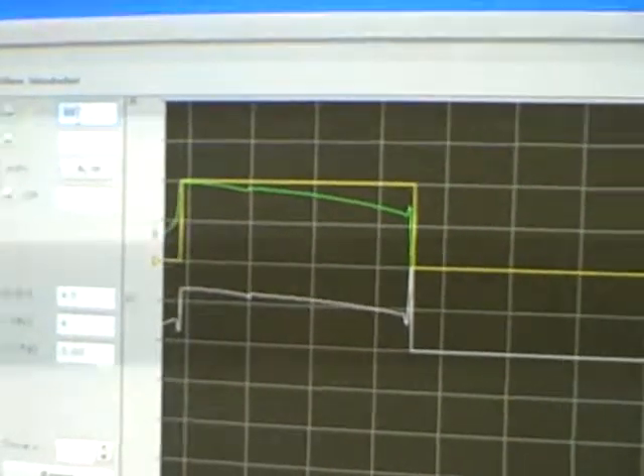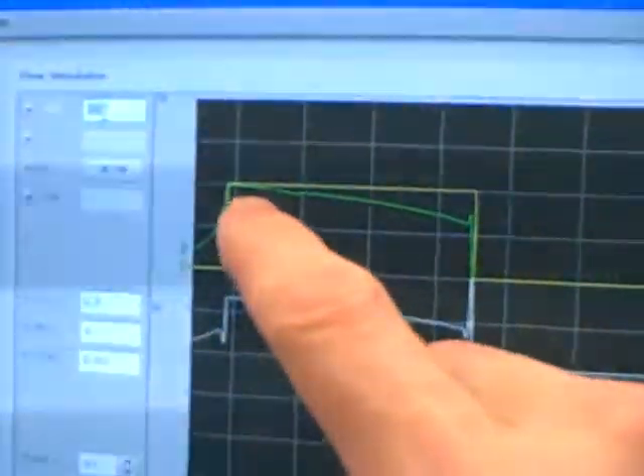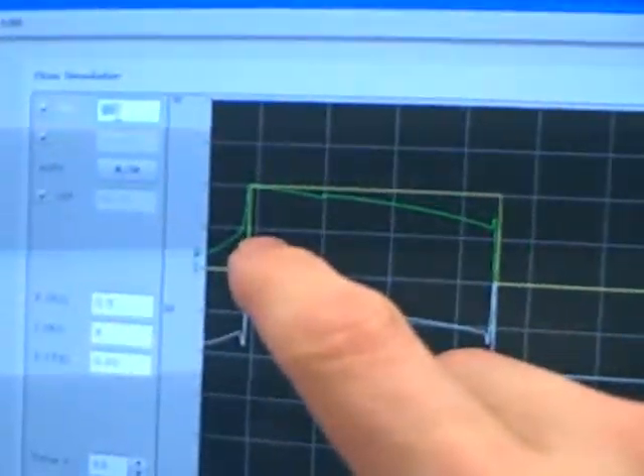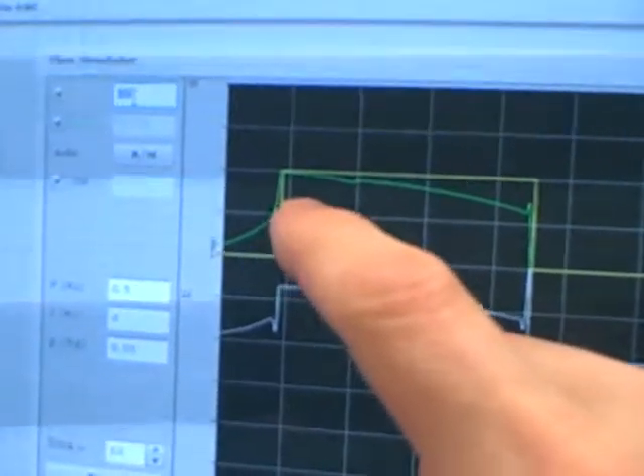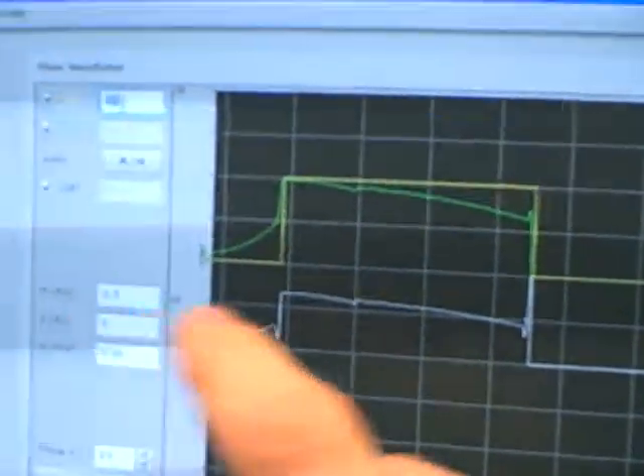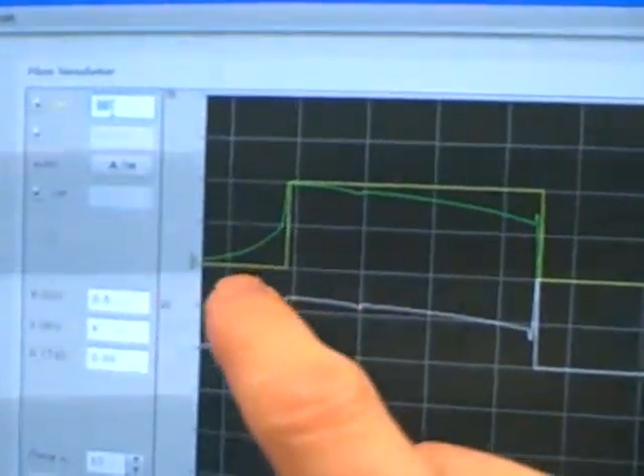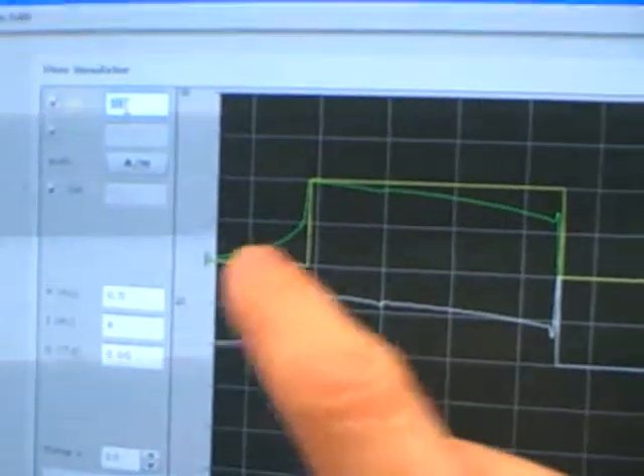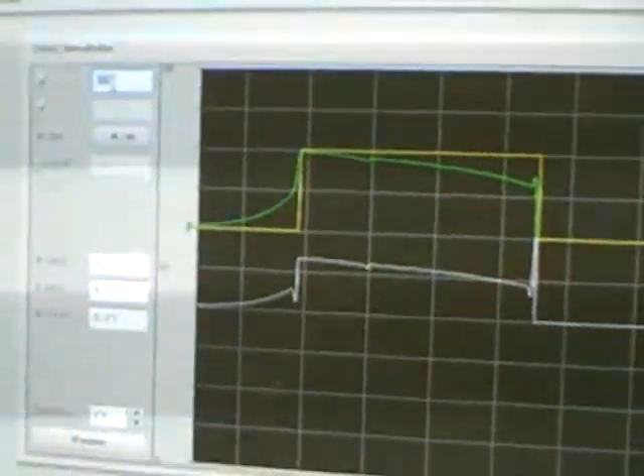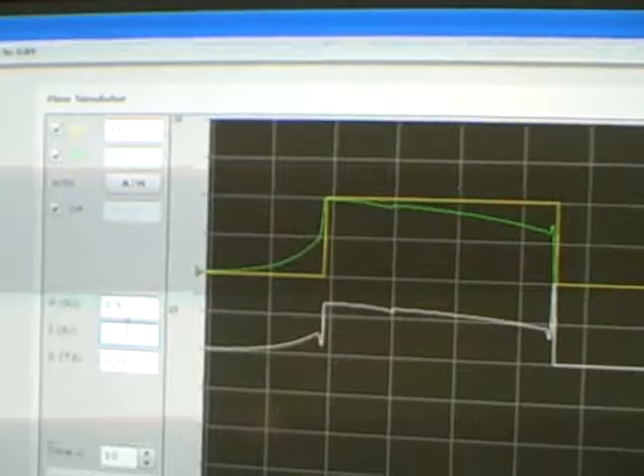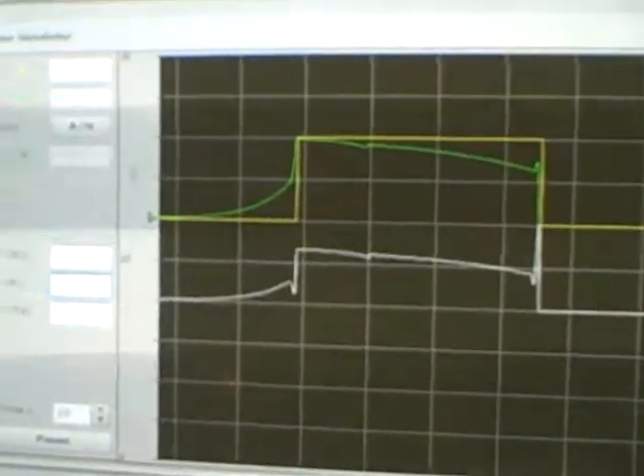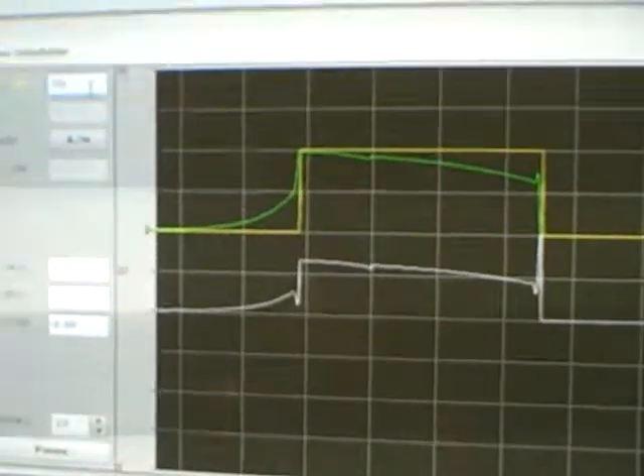Set point down to 30. You can see we took an immediate step with proportional action. No porpoising, no oscillation, that's because we turned our gain down. And we're still settling into set point, but it could go much, much faster. So I'm going to crank up my integral even more. I'm going to go 10 repeats per minute and change my set point back at 40%. We'll see what happens.